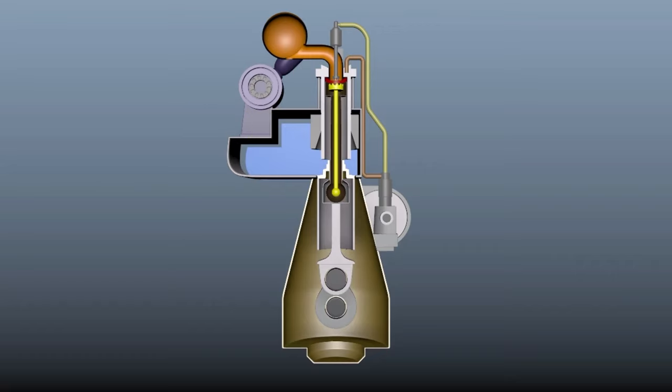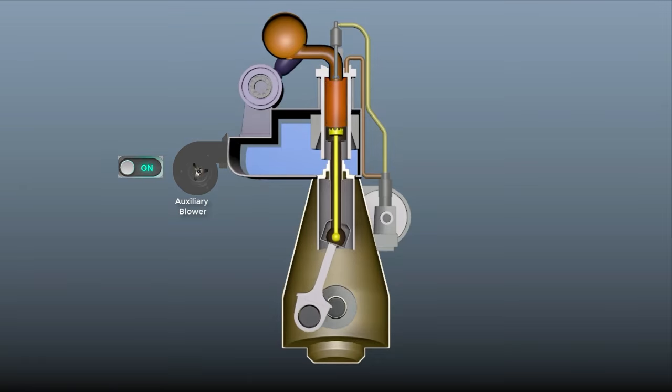Hence, additional blowers are installed which are switched on during the start of the engine. When the RPM of the engine reaches a range where turbocharger supplies fresh air, the blower is cut off.